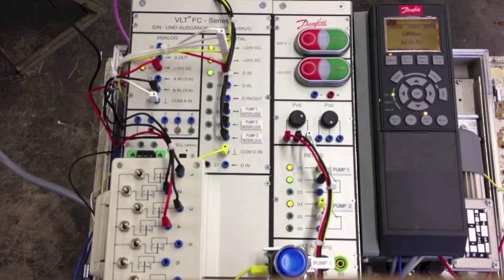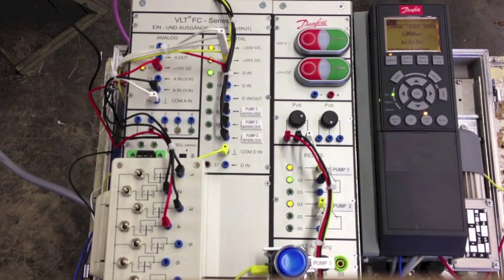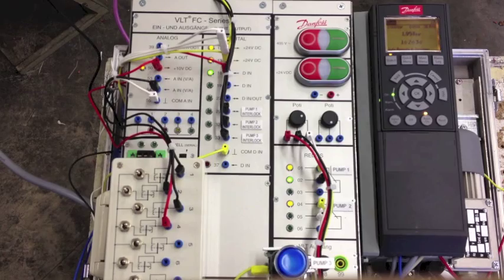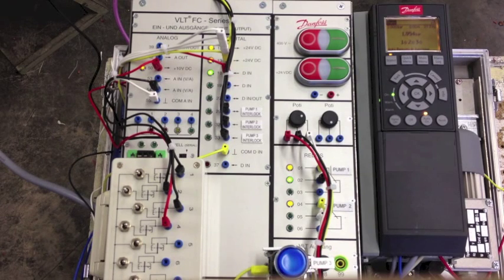As you can see the pressure is below the set point. The drive needs to start the second and the third pump.